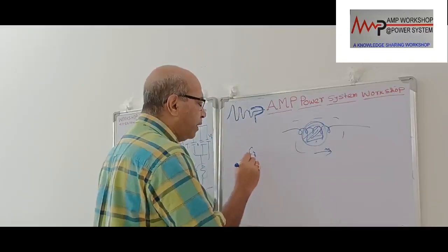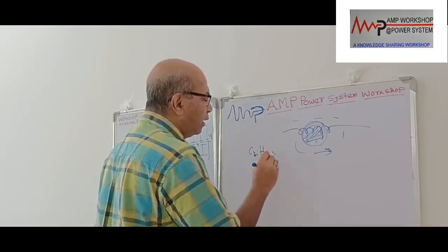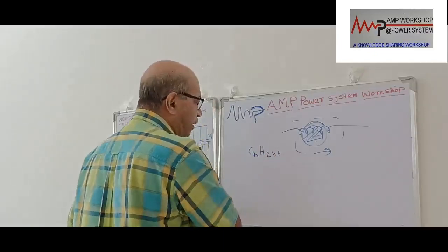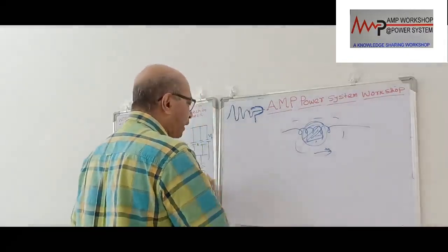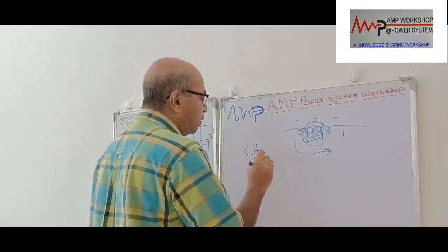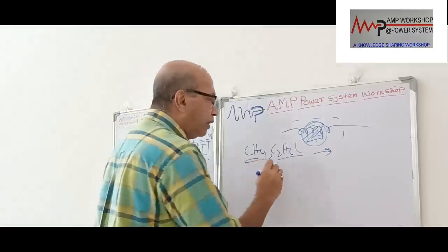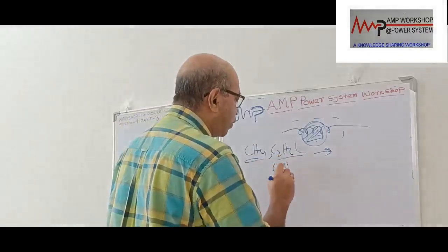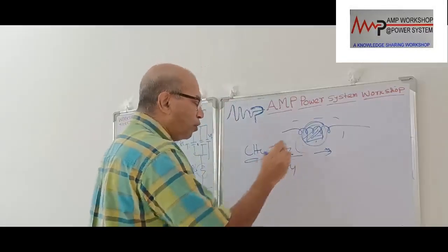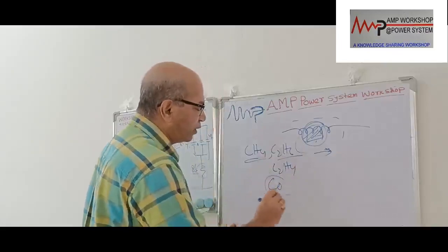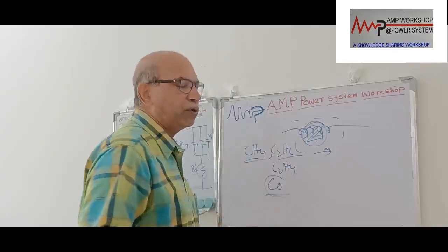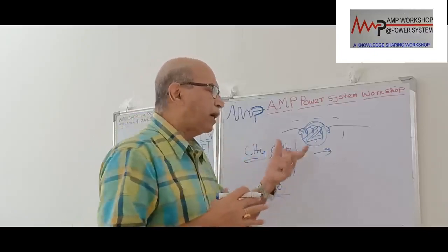Alkane means CnH2n+2, like methane CH4 and ethane C2H6. These two, methane and ethane, are produced. It produces ethylene also, C2H4. Then carbon monoxide is produced due to cellulose decomposition. All this gas is produced due to decomposition of the cellulose and the oil.